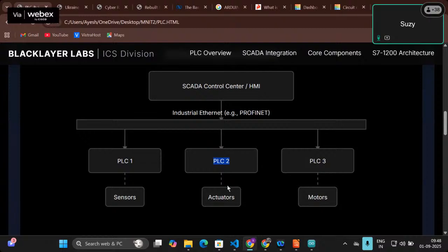This sensor gives data through Modbus to the SCADA, and then SCADA sends data to the PLC saying, this is the water level of the tank, and in order to maintain 80% of water, you need to fill the tank, and once filled, you can stop. So here we set a threshold limit of maximum and minimum water percentage so that the limits are maintained.